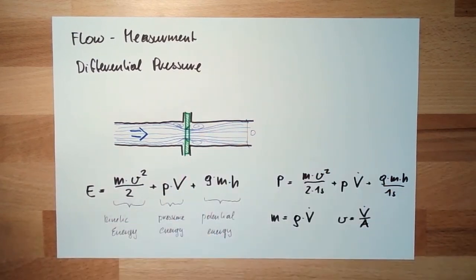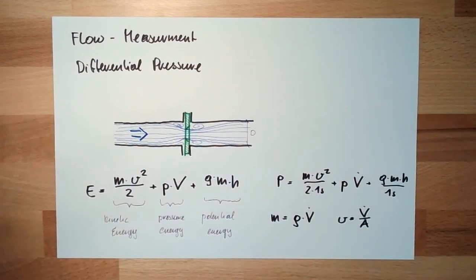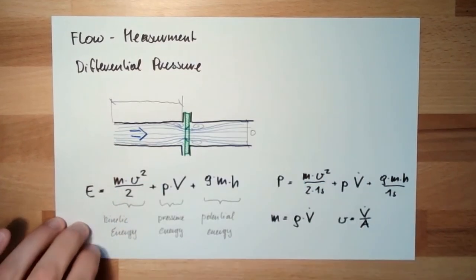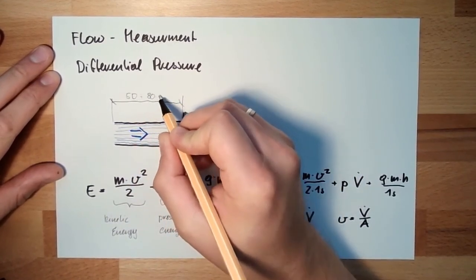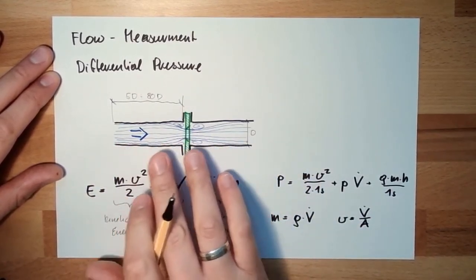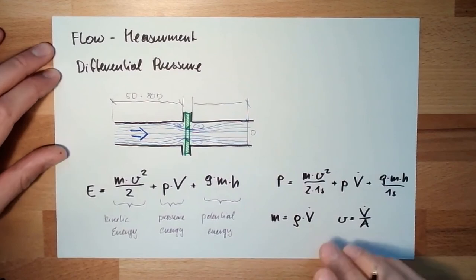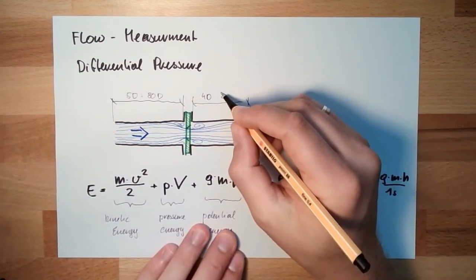The advantage is rather logical: there are no moving parts, it's adaptable for different sizes, and it works for most liquids, gases, and so on — it's a well-known principle. However, you need a straight pipe section before the measurement — about 5 to 80 times the diameter depending on the liquid, material, and sizes — and afterwards about 4 to 8 times the diameter.